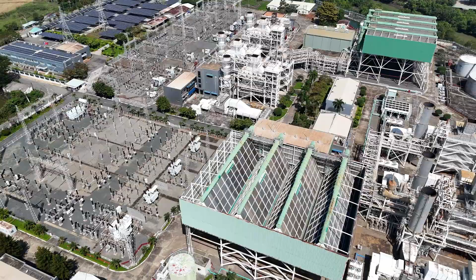A grid whose demand could be modeled with reasonable confidence months in advance, because the consumers at the end of the line were running appliances and factory equipment whose behavior was well understood. A grid where the single greatest risk was a component failure during a period of peak but foreseeable demand. N-1 does not require the system to survive two simultaneous failures. It does not require the system to survive a component failure during conditions that fall outside its historical design envelope, such as temperatures 40 degrees below what the equipment was built to handle.